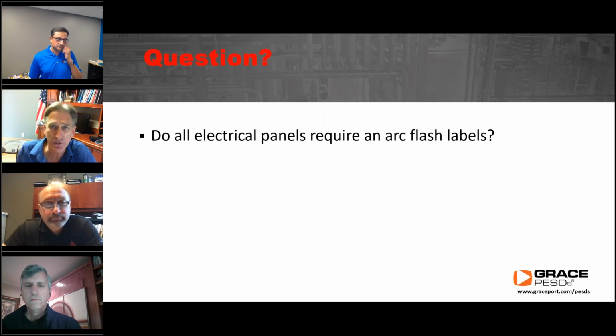It says such as switchboards, switchgear, panelboards, industrial control panels, meter socket enclosures, and motor control centers that are in other than dwelling units. Of course, this does not apply to dwellings. And here's the key part: it's likely to require examination, adjustment, servicing, or maintenance while energized. It shall be field or factory marked. The factory part was added a couple of editions back. It used to say it had to be field marked. This is the general rule, the general arc flash label, field or factory marked to warn qualified persons of potential electrical arc flash hazards.